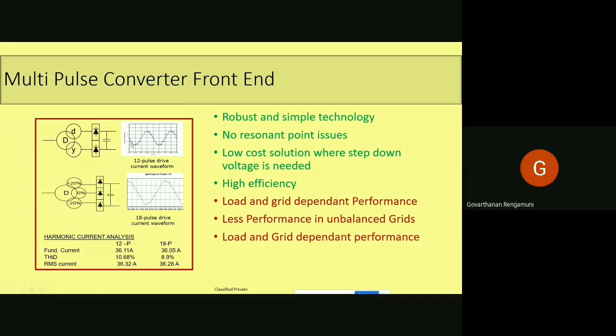Considering the primary current, because of this phenomenon, you will be getting a more close sinusoidal waveform. So once we reconstruct this waveform into sinusoidal, automatically what happens is your harmonic distortion at the PCC level is getting corrected. So this is how the 12 pulse works. So the multiples of pulses will reduce the harmonic frequency. Already we know. So the multiples will grow like 18 pulse, 24 pulse, something like that.